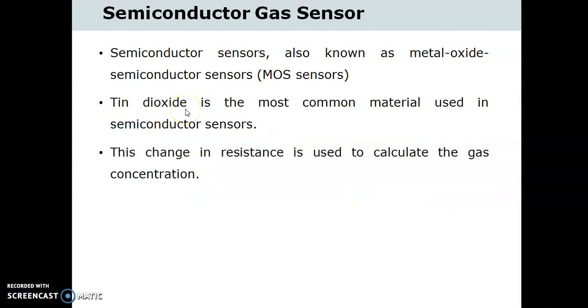Tin dioxide is the most common material used in the semiconductor sensor, and the electrical resistance in the sensor is decreased when it comes in contact with the monitored gas. This change in resistance is used to calculate the gas concentration. The resistance of tin dioxide is typically around 50 kOhm in air but can drop to around 3.5 kOhm in the presence of 1% of methane.